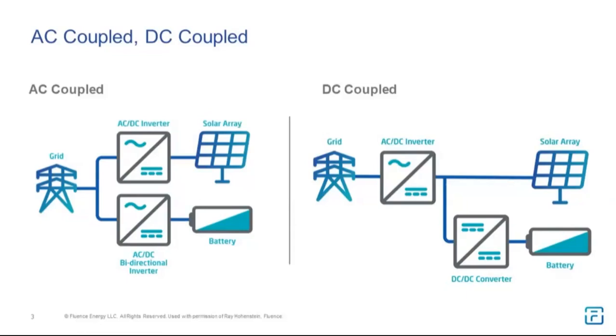That seems simpler, but you do end up with operational flexibility problems that make this design less interesting and less desirable in many cases. For example, if you separately offer both to the market, but they're constrained at the point of interconnection to 100 megawatts total, how do you deal with the simultaneous dispatch of those in the market sense? That's a constraint, but you don't want to set a price inside your own power plant and be competing with each other, lowering the price of your PV and storage value. So it can't be treated like a normal constraint in the system.